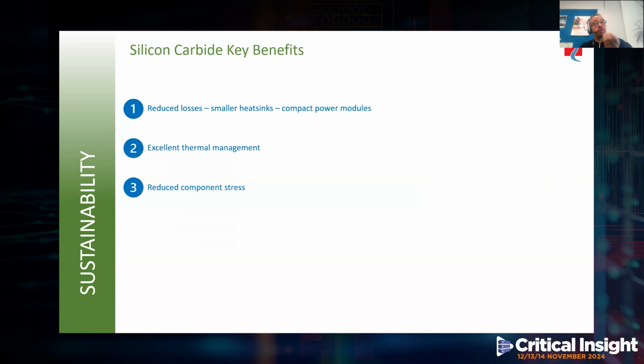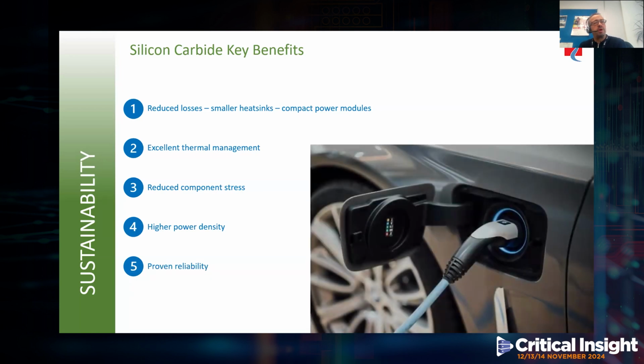Now, what other benefits does it provide? Well, the reduced losses mean smaller heat sinks, resulting in a compact design. They have excellent thermal management, so the devices are extremely stable. The overall component stress is reduced, meaning increased reliability. It provides a high power density, resulting in high power levels from very small devices. And most importantly, silicon carbide is a proven and reliable technology, which is used extensively throughout the EV and industrial markets, where you can appreciate the operational conditions can be extremely harsh, especially compared to a UPS system's operation.